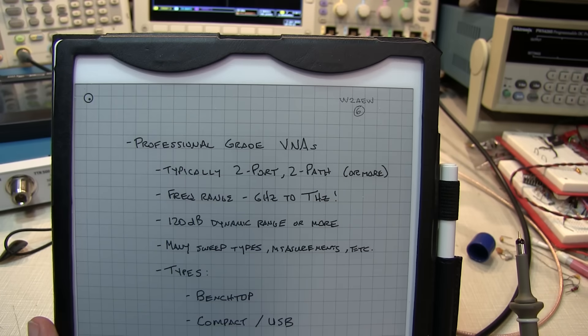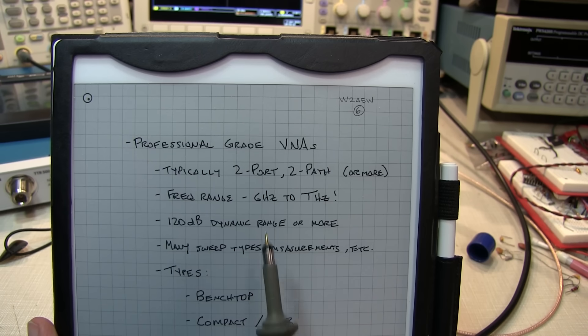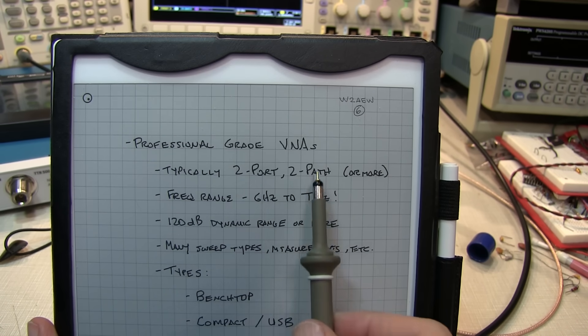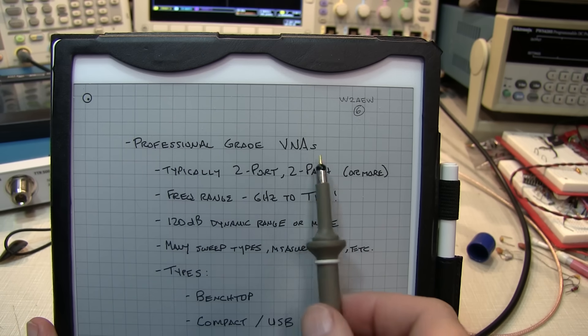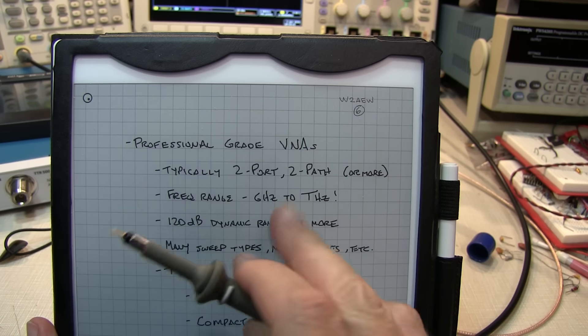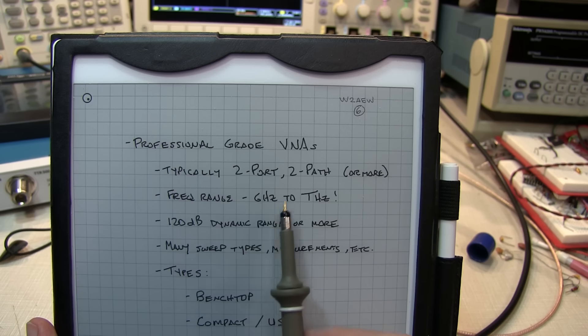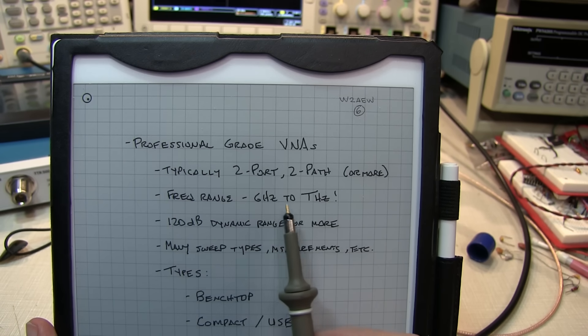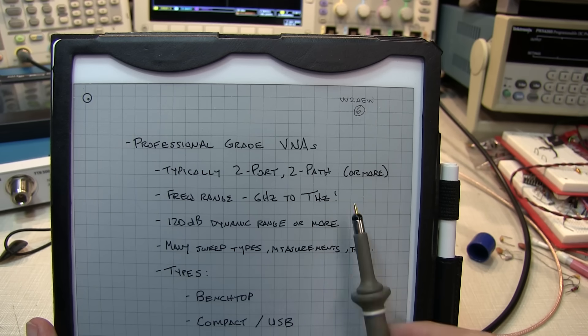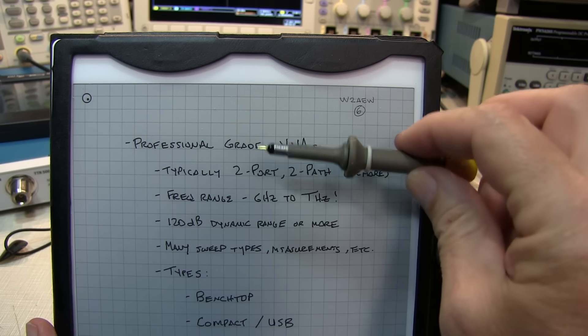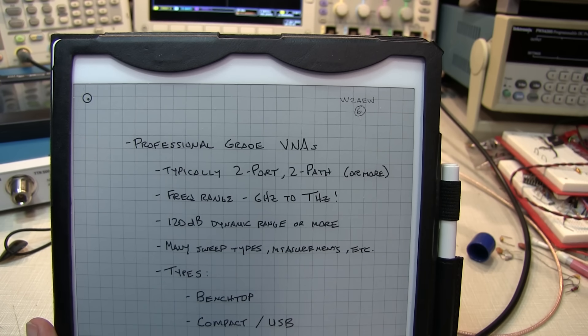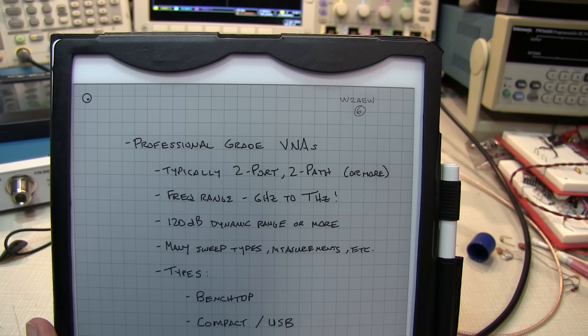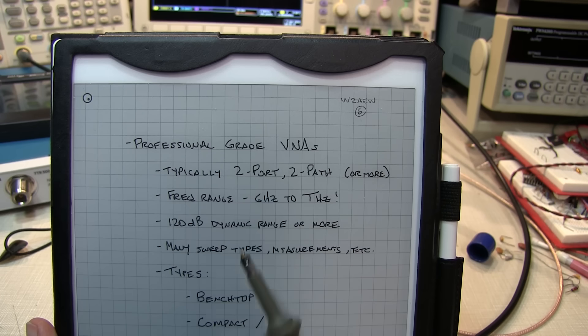There's a wide variety of vector network analyzers available on the market. Most professional-grade VNAs are two-port, two-path devices, meaning they have two RF ports. You can hook up a device input and output to the two ports and measure reflection off of either port and transmission in each direction without having to disconnect and reverse the device. Most VNAs have a frequency range of a couple of gigahertz, but they're available up to even terahertz — though that costs big bucks. Dynamic range is typically 120 dB or sometimes much better. There are many different sweep types; some can sweep power to look at compression characteristics of amplifiers.